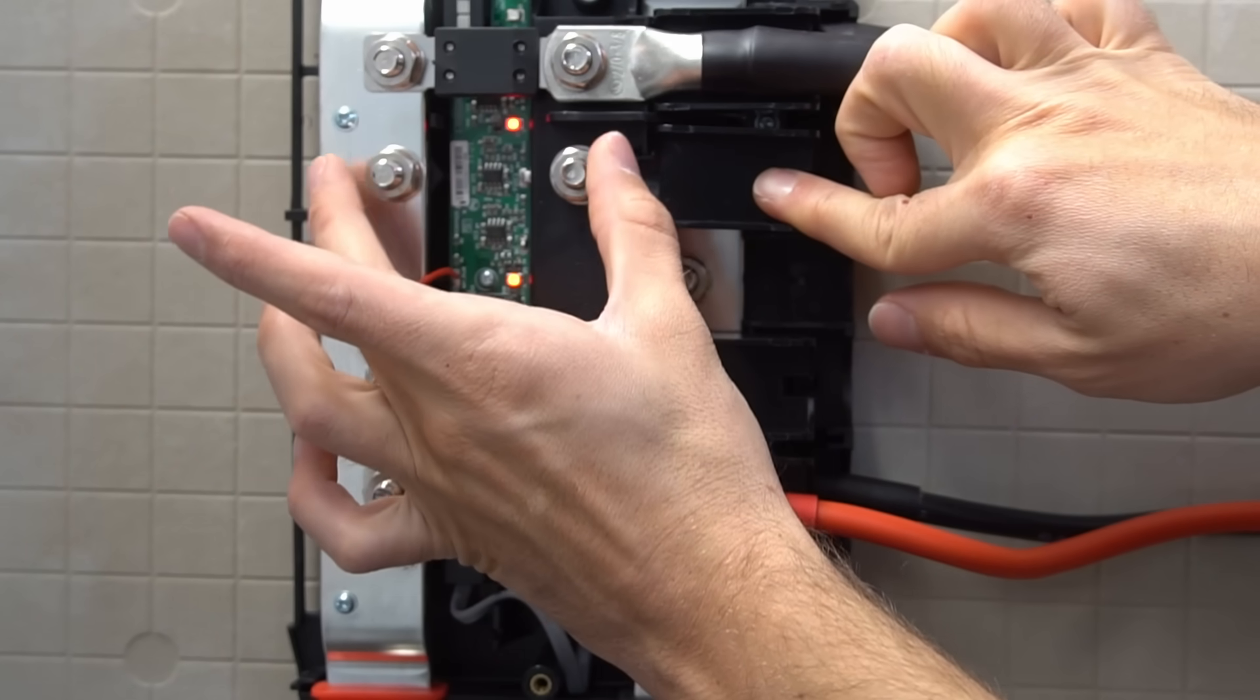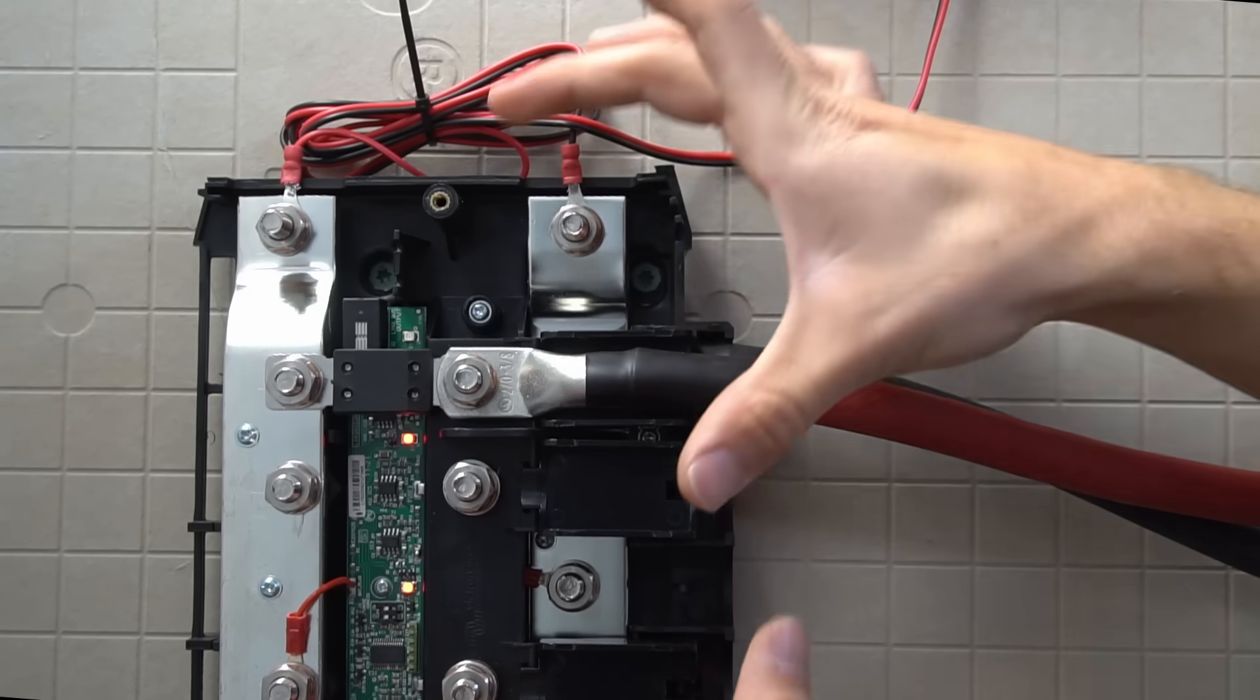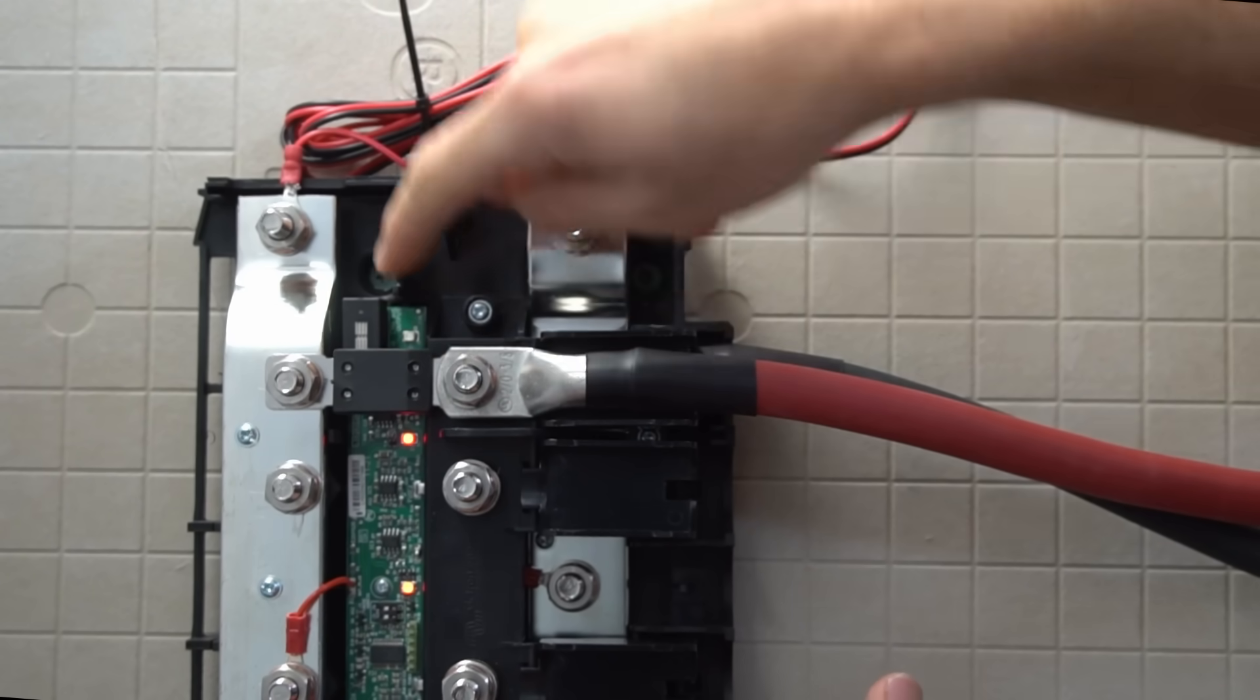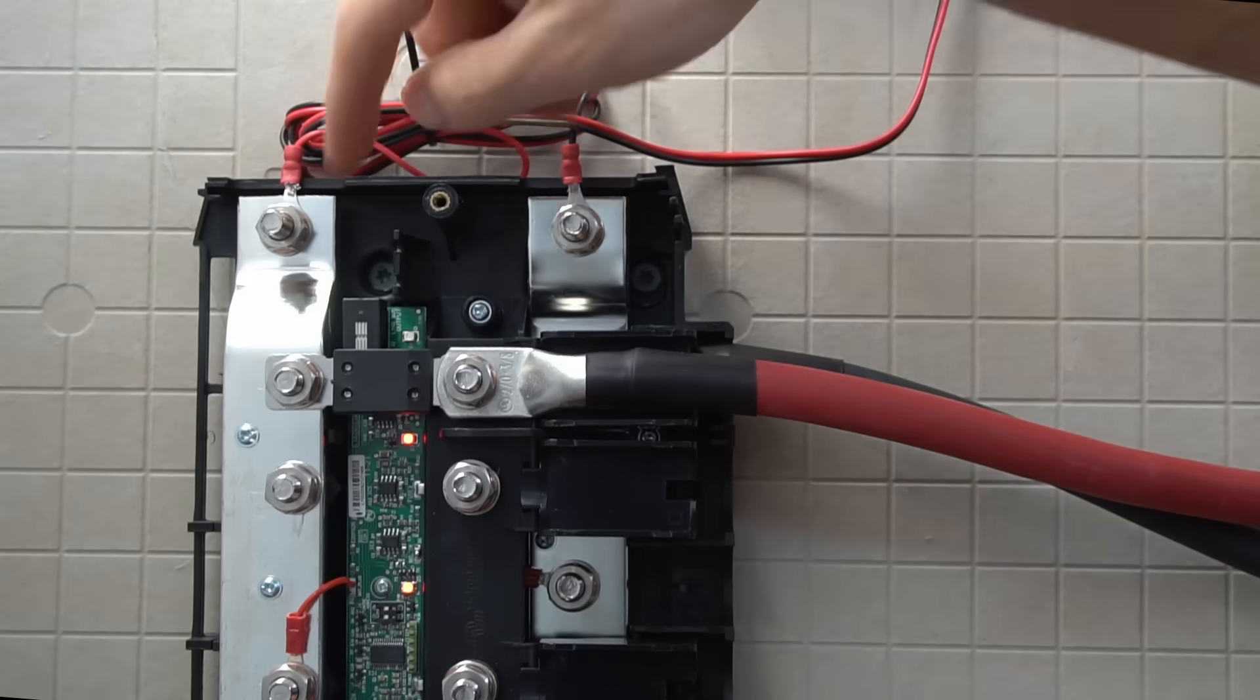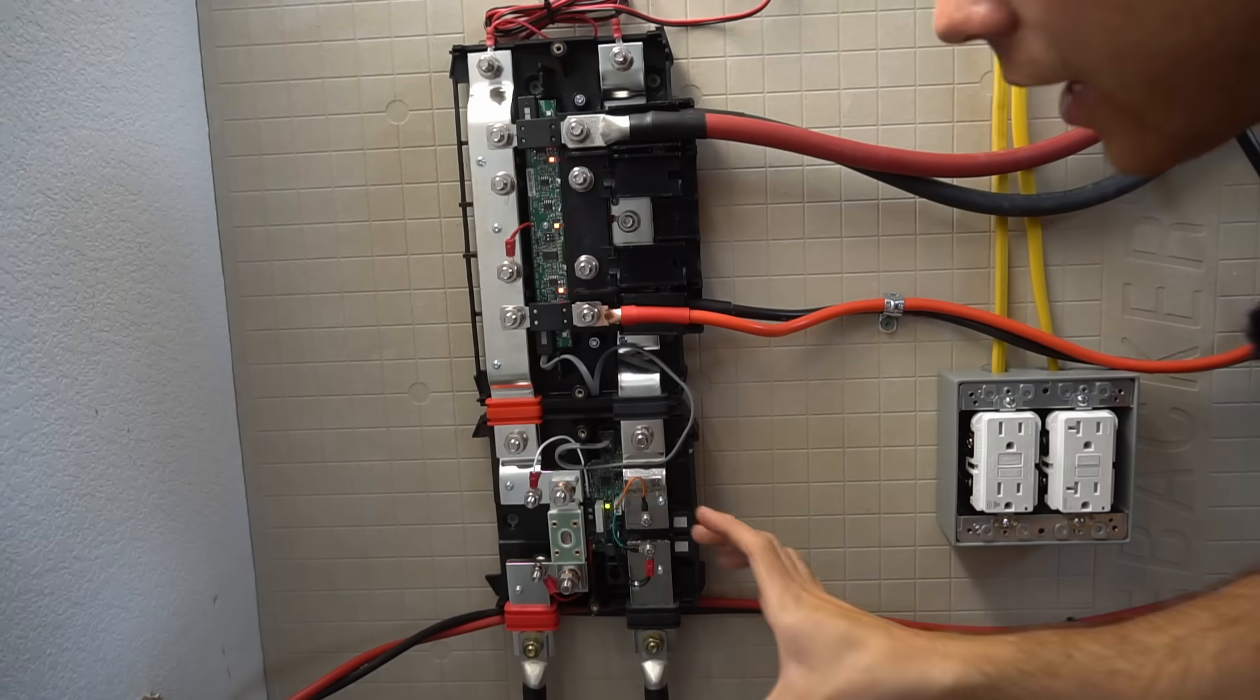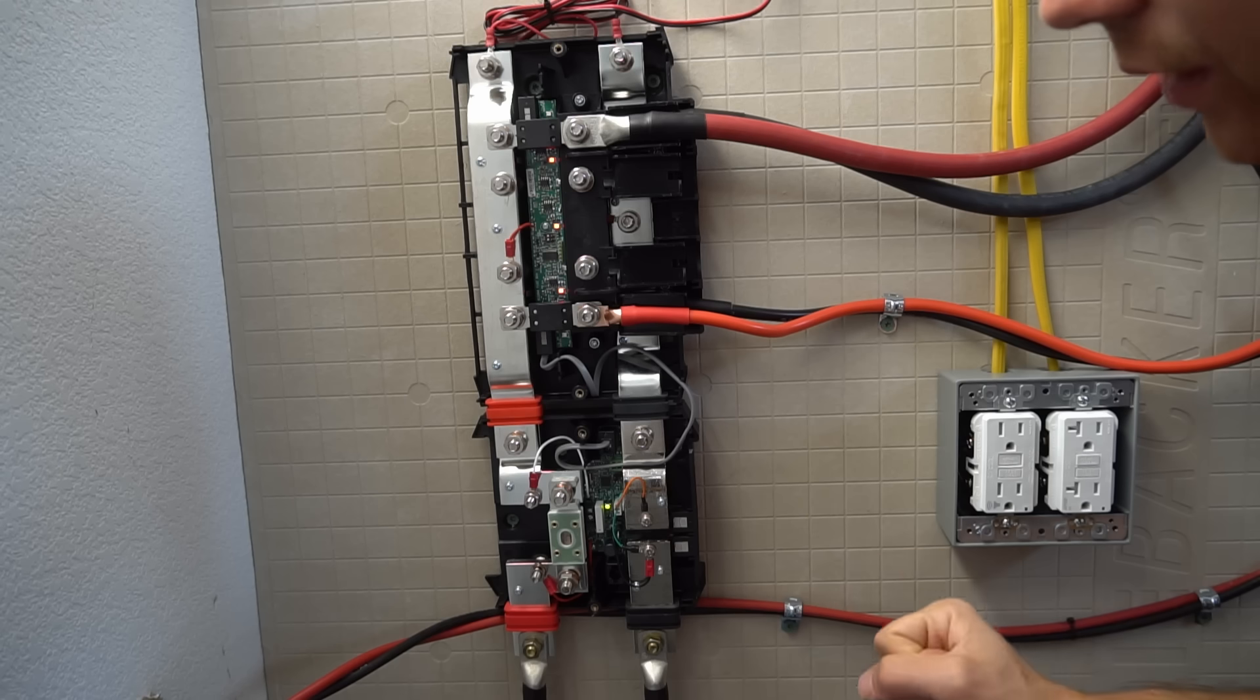And you can see the black cables in the back that are connected to the negative bus bar. Now when you want to connect the positive you put this cover down. You put a fuse right here for your load and then you connect it right here just like this one. Now if you want to add a second distributor up here you can also use a communication port to connect the whole system together. So small gray cable from here up to the first communication port on the other distributor. This entire system is connected with this communication port.